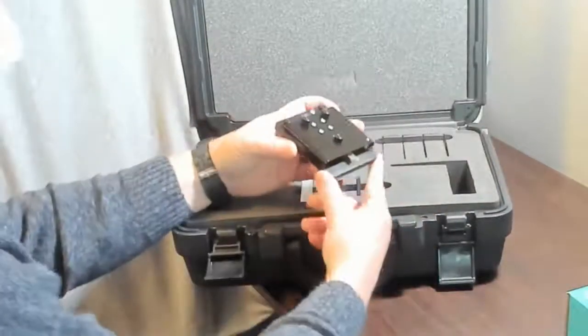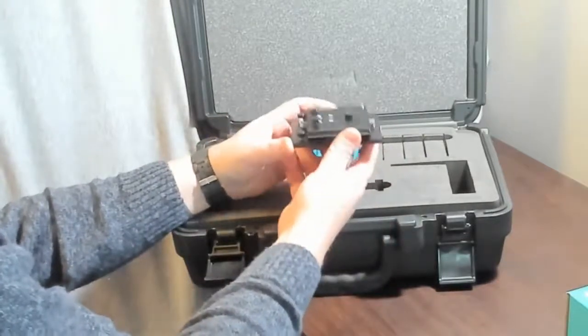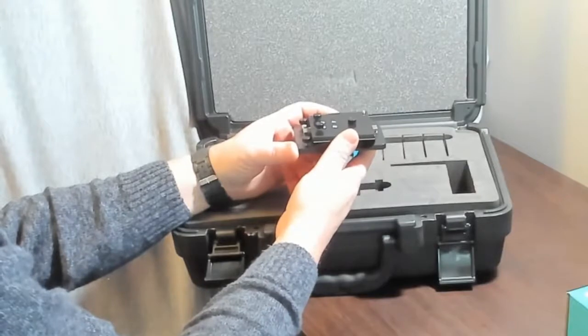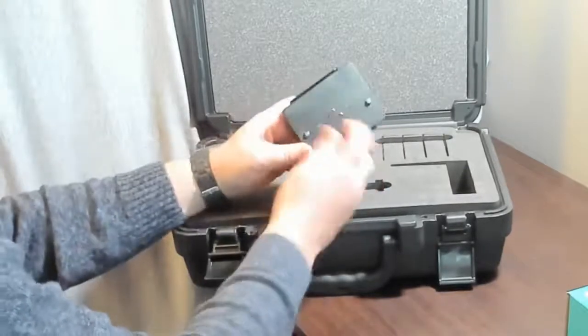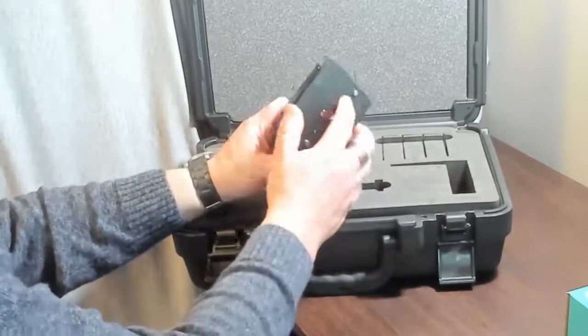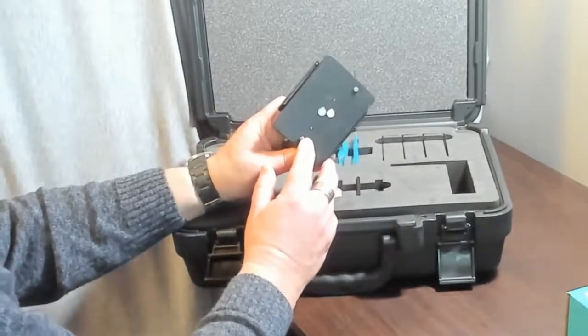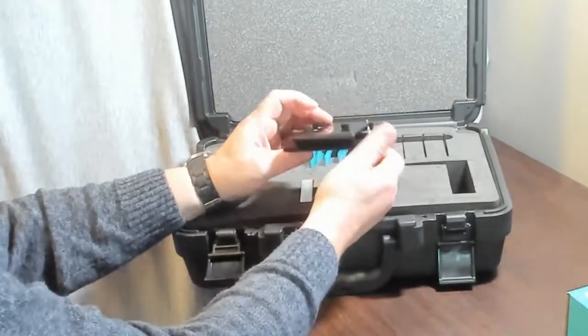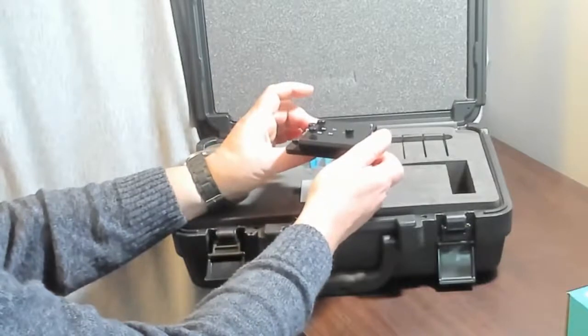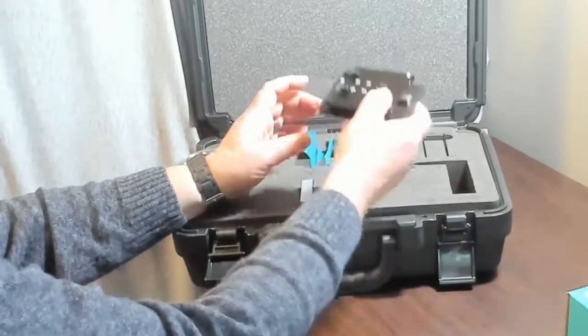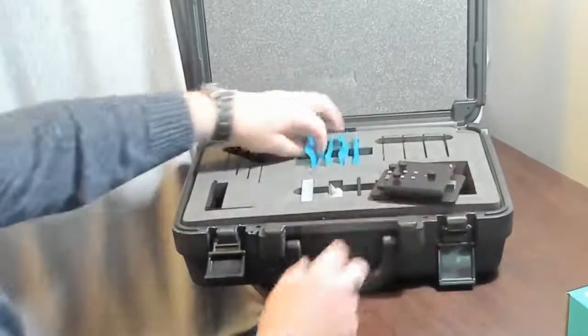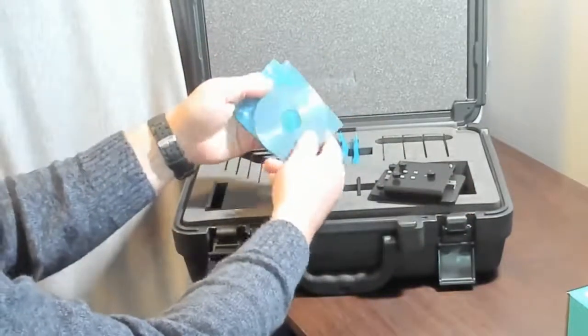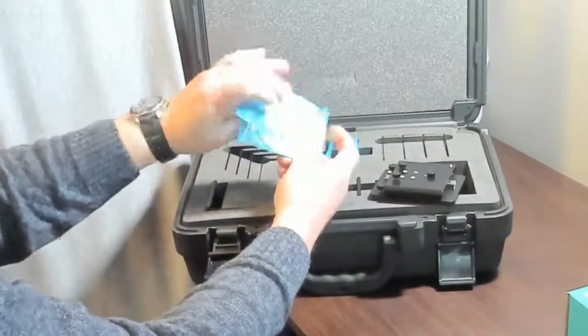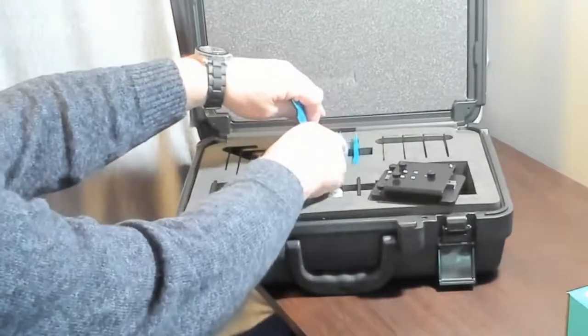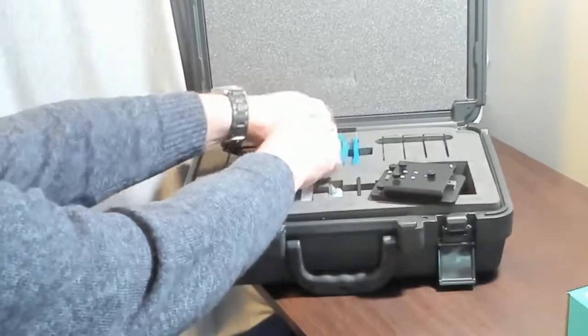And then the key here really is this piece, which will go into the transmission chamber and hold a variety of fixtures to hold our samples. Let's take a look at that. It's got a couple of magnets on the bottom because that's what's going to lock it in place. It also has a couple of pins here that will align with holes recessed in the transmission compartment, and then combined with the magnets will lock it in place depending upon what kind of measurement we need to do. So we'll take a look at how we're going to use that in just a second here. We also have 4 different aperture plates for the front of the device, and we'll talk about why the necessity of those and why they are different than the reflectance ones a little later in this video.